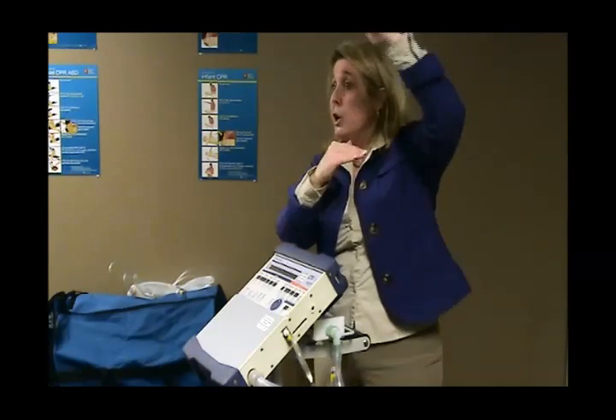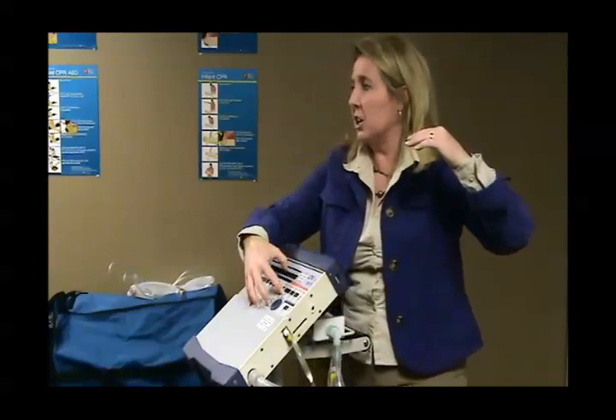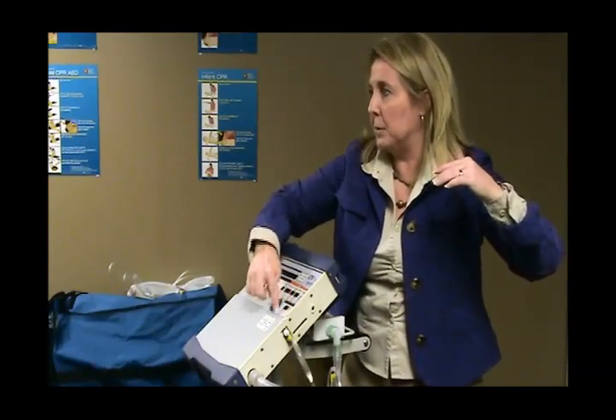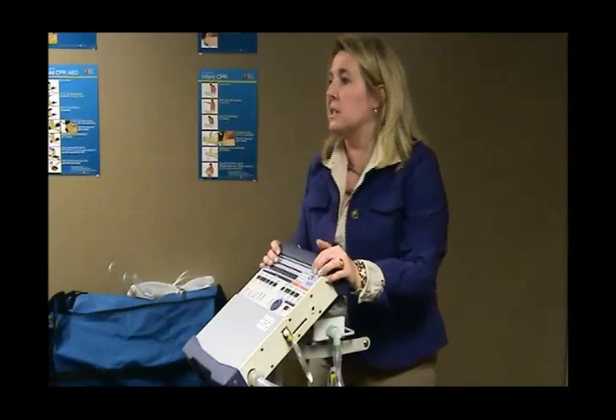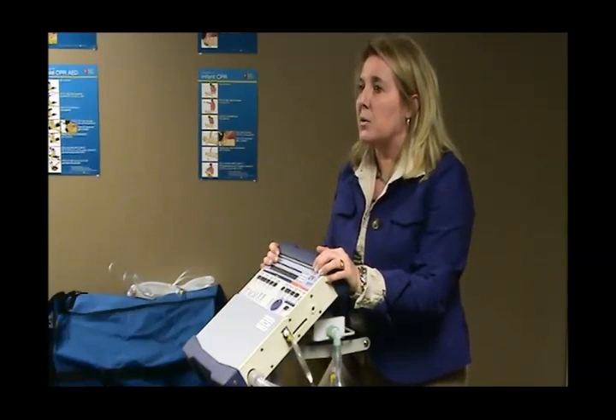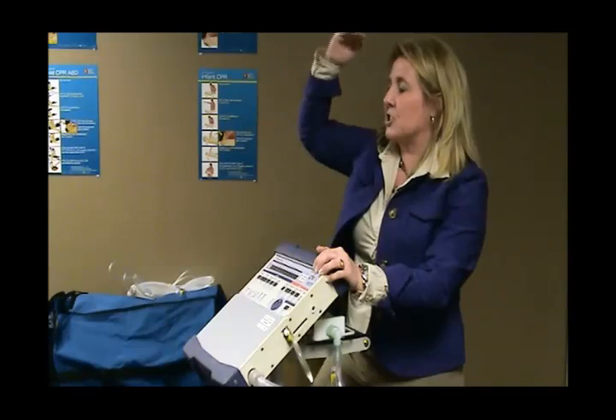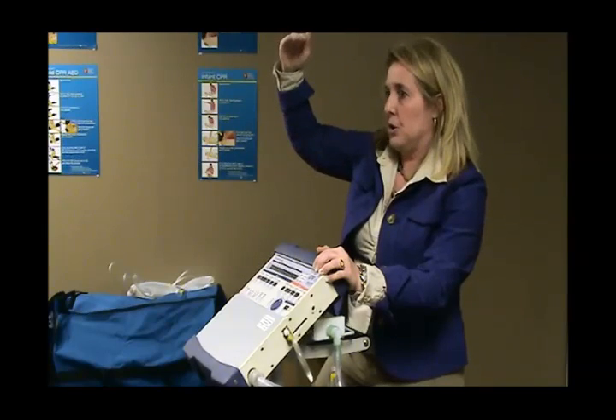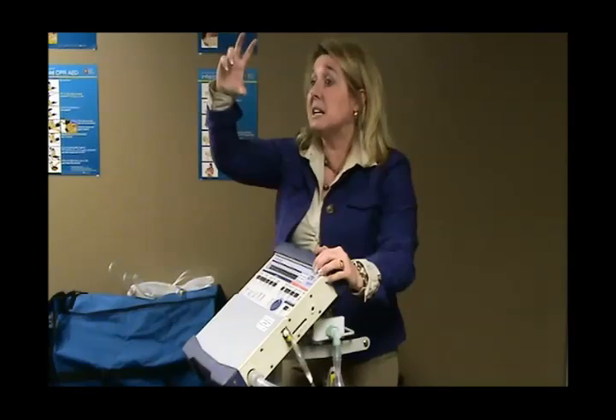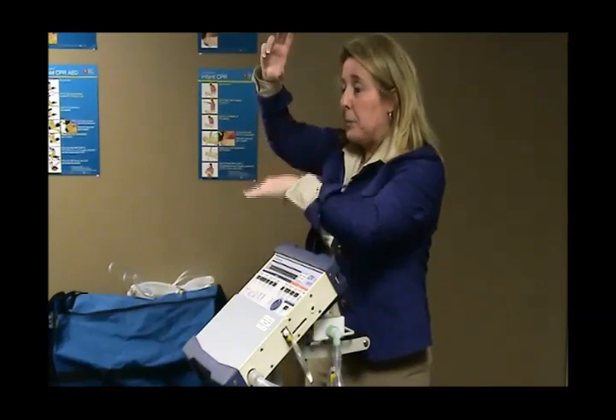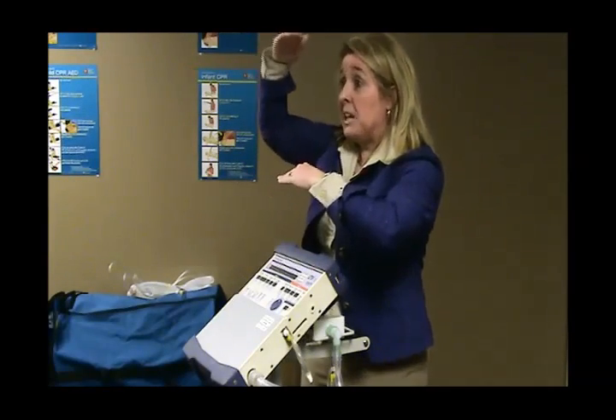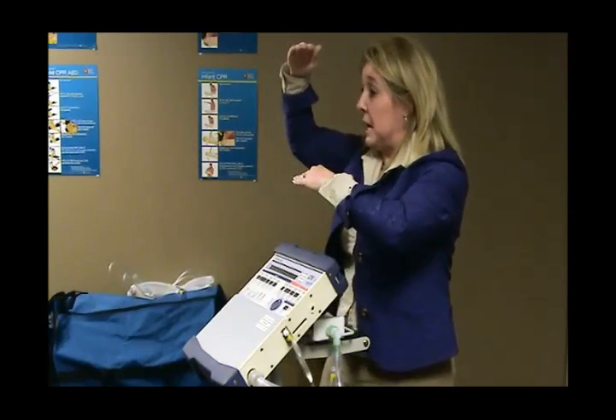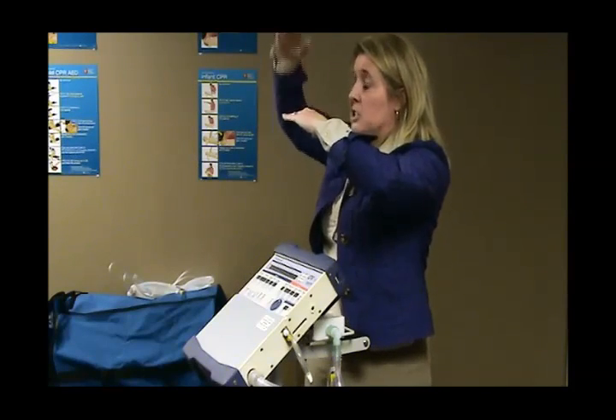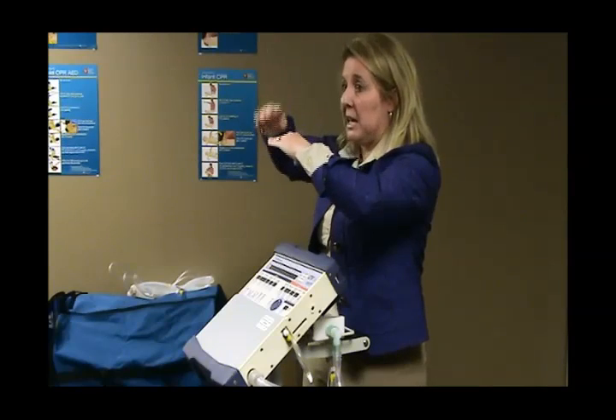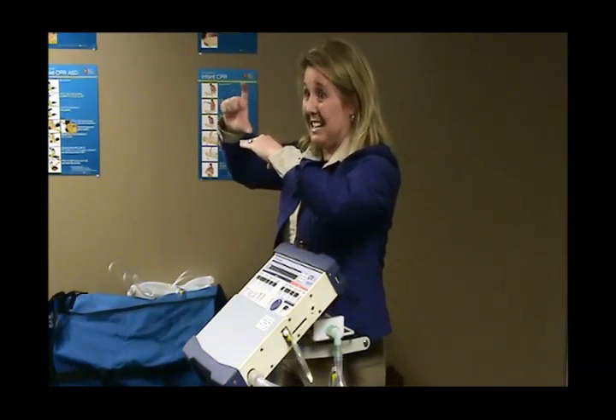Then our normal peak inspiratory pressure should be about 20 on an LTV ventilator with internal PEEP, with dial-in PEEP, okay? If it's on the older style of LTV that has an external PEEP valve, when you set the pressure, that is actually the peak inspiratory pressure, okay? So if I set it at 15 and I dial in a PEEP of 5, now my peak inspiratory pressure is still only going to be 15, my PEEP is 5, so my change in pressure, or my delta P, my ventilating pressure, is only 10.